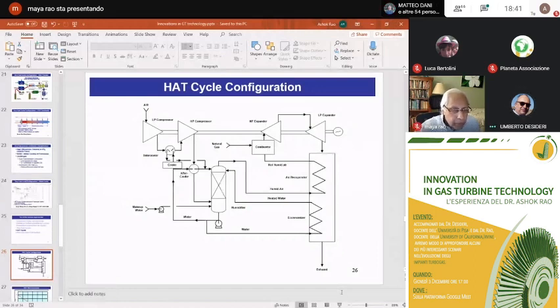As far as I can tell, they show two streams being preheated against the exhaust. I haven't seen the details on the recuperator design, but in a combined cycle you can stagger these—for example, the reheat and superheat coils. You can have a portion of the reheat coils followed by a portion of the superheat coils, repeating the sequence. I'd think you could do something similar here.